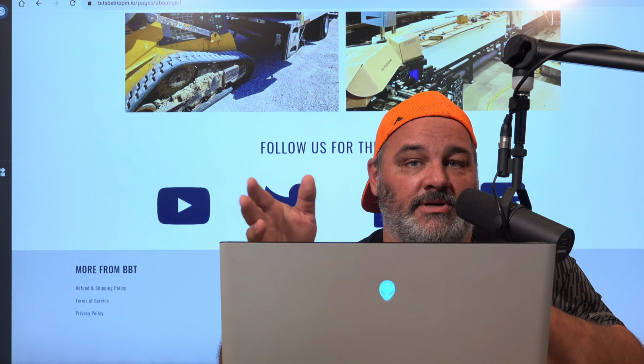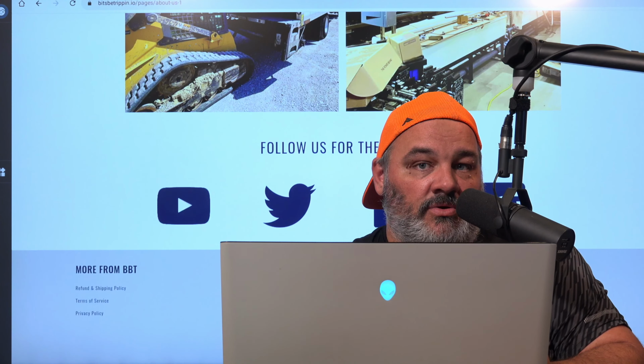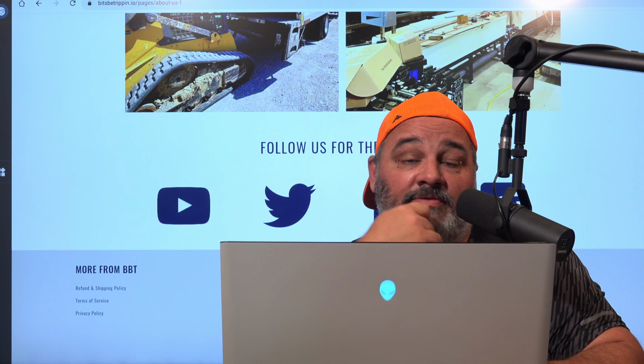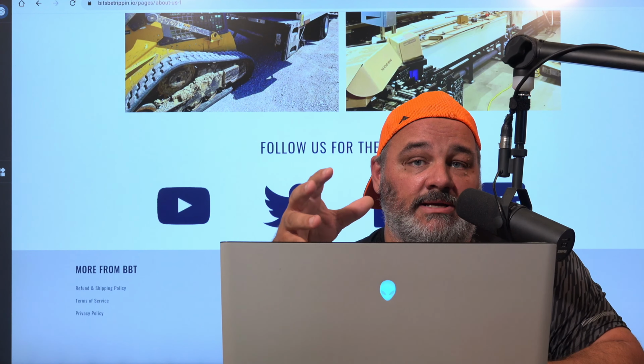The backup systems, power systems, like for us, it was kind of an iterative thing. We had a pretty good architecture design for our IT infrastructure and our security architecture. However, when we started curtailing, sometimes we would shut down, and part of that curtailment would take down one of our primary switches, which then we lost our cameras on. And it was like, well, wait a minute here. We have to refigure this.